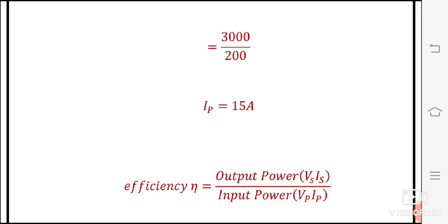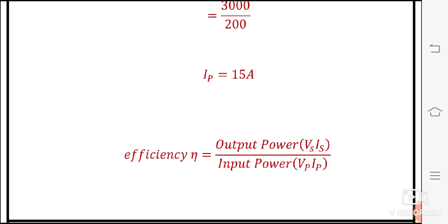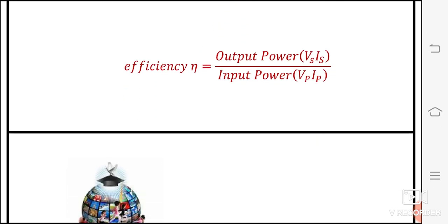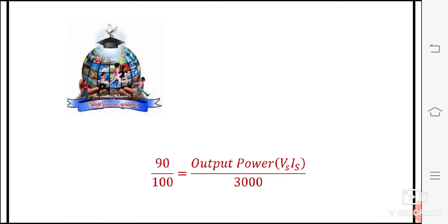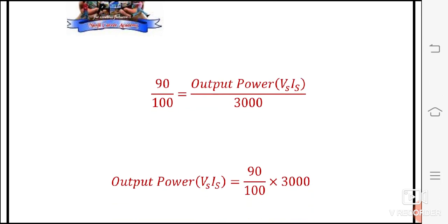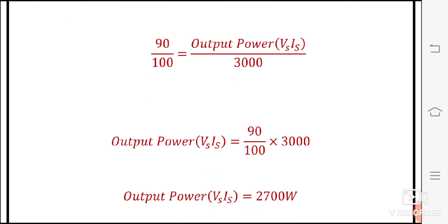Efficiency is defined as output power divided by input power. Output power is the product of secondary voltage and secondary current, and input power is the product of primary voltage and primary current. Input power is given as 3000 watts, and efficiency is 90%. So: 90 divided by 100 equals output power VS × IS divided by 3000. From this, output power is equal to 90 by 100 into 3000, which gives output power equal to 2700 watts.